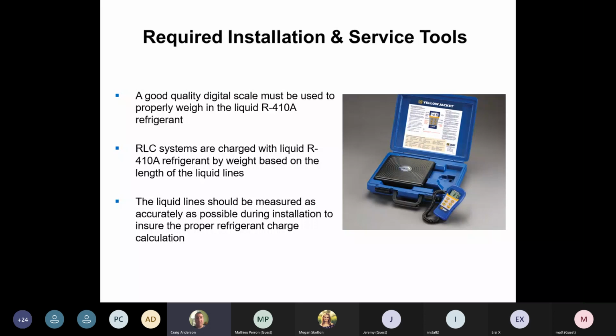So if you're doing a new install or you're working on a unit where you doubt what the last guy did or what the guy put in and took out, take the gas out and weigh it in. It's the only proper way to do the system. If you weigh the gas in to the factory charge, add your gas in to what the unit recommends for the longer line length, that is out of the equation. I have the right amount of gas in. Let's move on. Let's check airflow. Let's check something out. Take the time, weigh the gas in, take it out of the equation, move on to what's going on next.